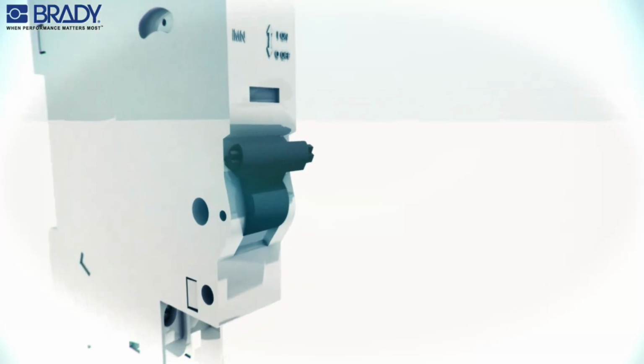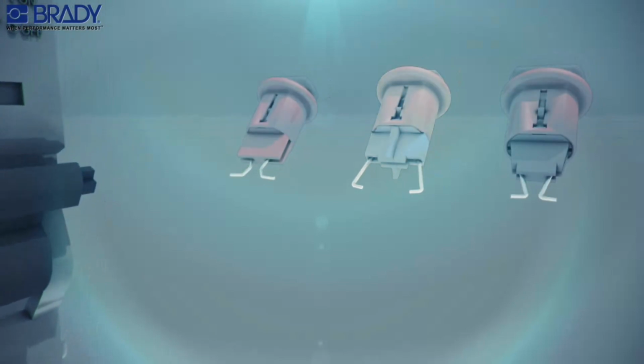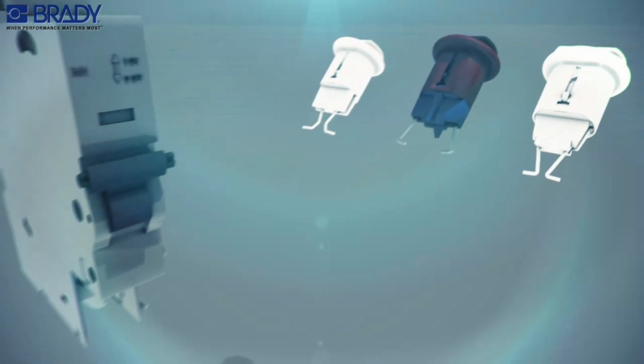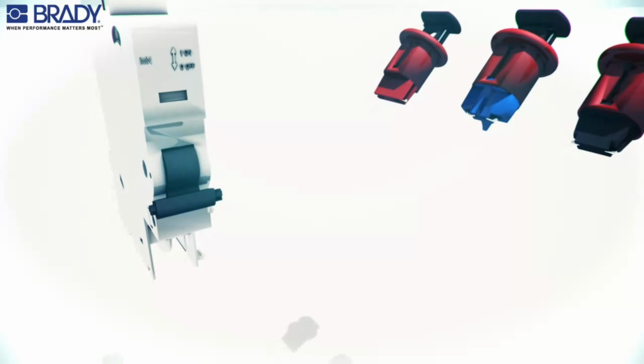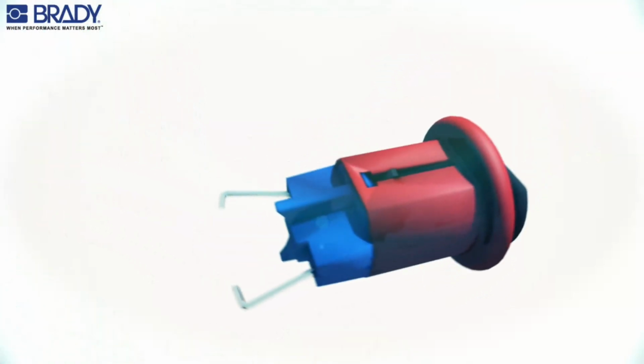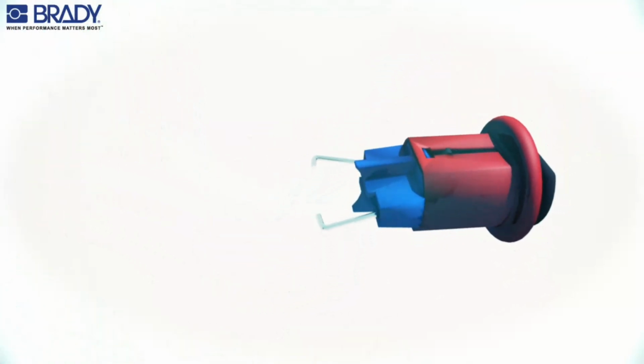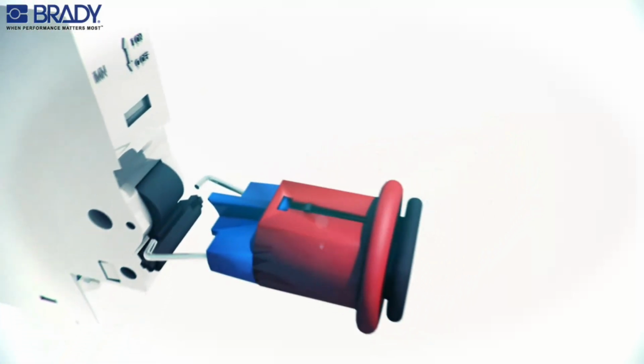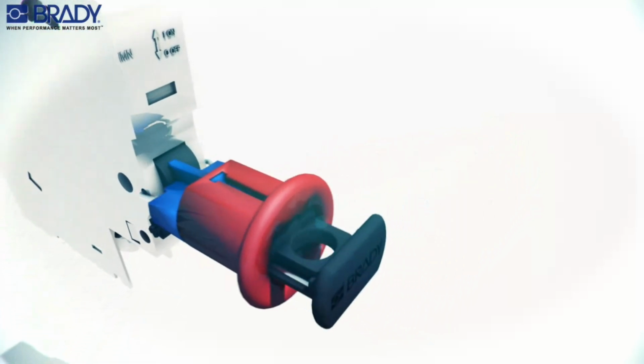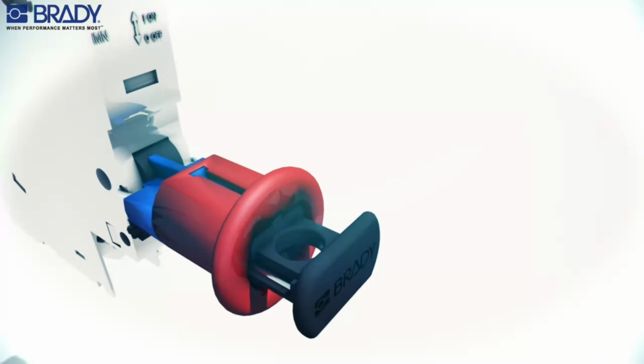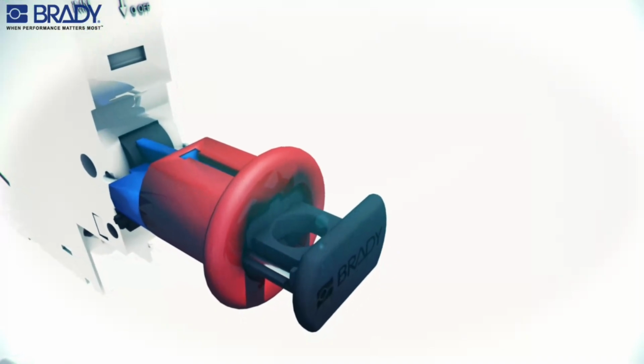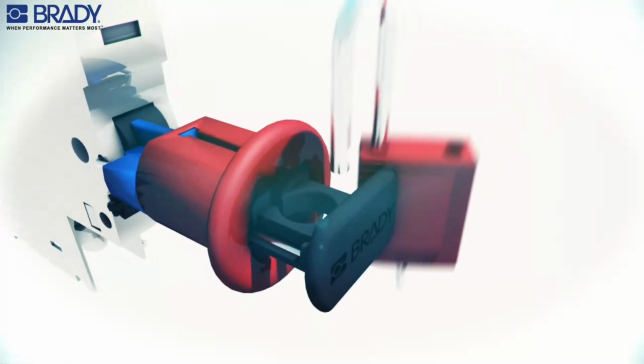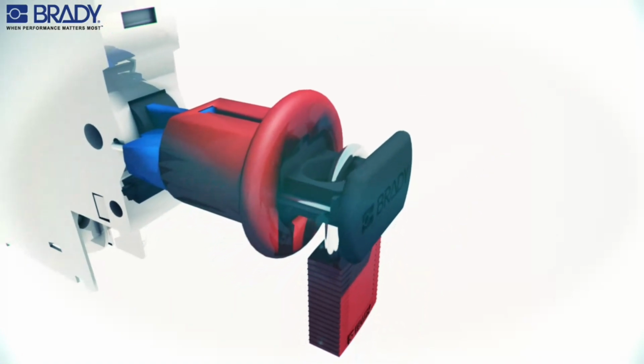Locate the small holes in the center of the circuit breaker casing and select the appropriate pin-in or pin-out circuit breaker device. Place the circuit breaker in the off position, then press the lockout device push button to disengage the pins. Position the pins into the small holes of the casing by releasing the push button, and attach a Brady safety padlock through the lockout device hole to complete the lockout.